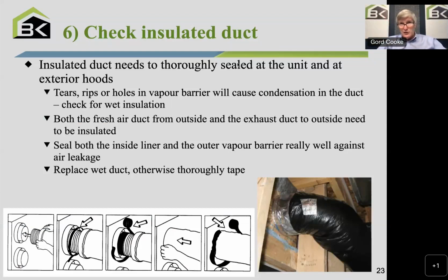It's actually difficult to dry it out, which means I need to put a new piece of flex duct from the outside back to the unit. You might say, could I just splice that wet spot? The problem is we don't exactly know where the rips or tears are. So typically you have to change the whole duct. But that's unusual in an existing building that's been working fine, unless there's been some changes in the basement that may have caused a problem. So, it's something to check on, if you will.